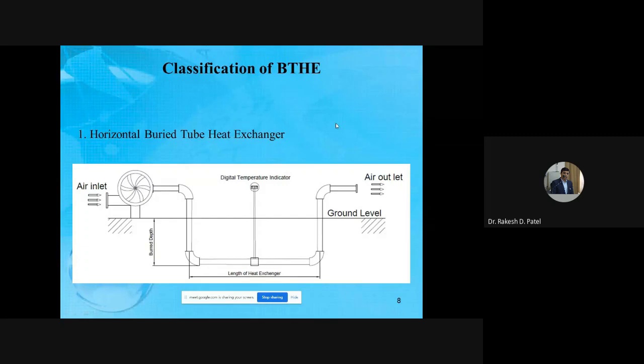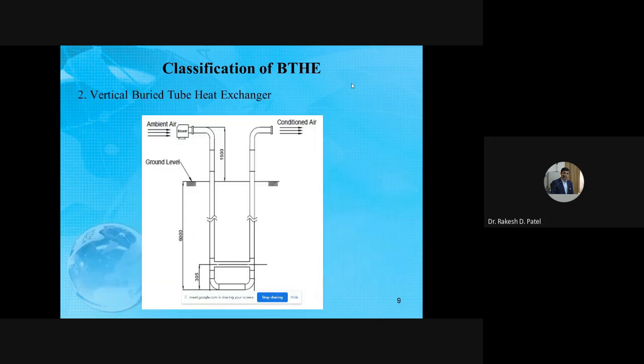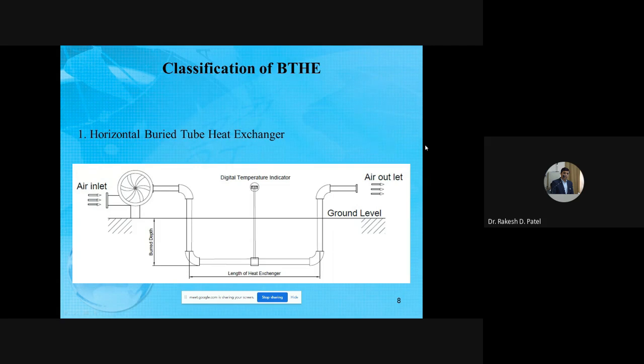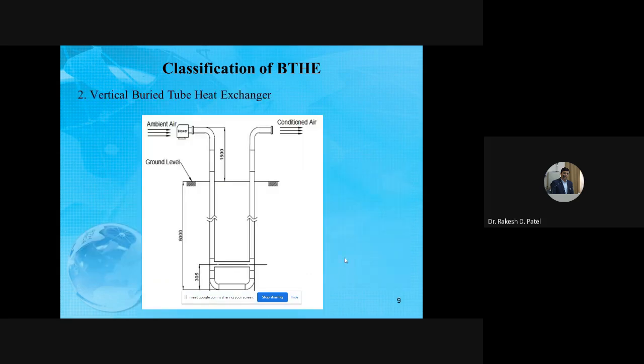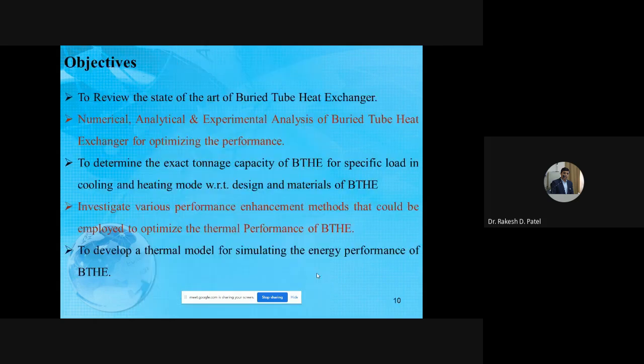Now, the classification of the heat exchanger. First of all, the classification of a heat exchanger based on its alignment: the horizontal buried tube heat exchanger, and the vertical buried tube heat exchanger. In the horizontal buried tube heat exchanger, the major portion of the heat exchanger is horizontally buried at buried depth. Otherwise, the principle and working of both heat exchangers are the same. In the vertical buried tube heat exchanger, the major part is buried vertically from 3 to 10 meter from the ground surface. So basically there are two major classifications of the heat exchanger: the horizontal and the vertical buried tube heat exchanger.